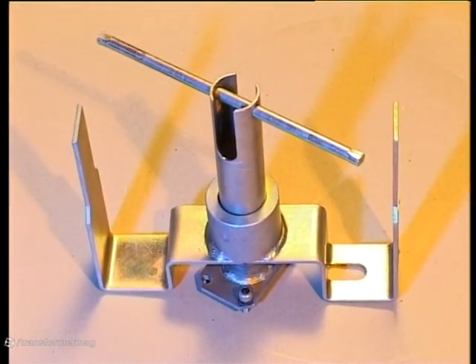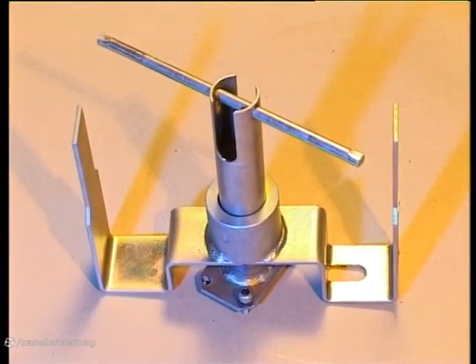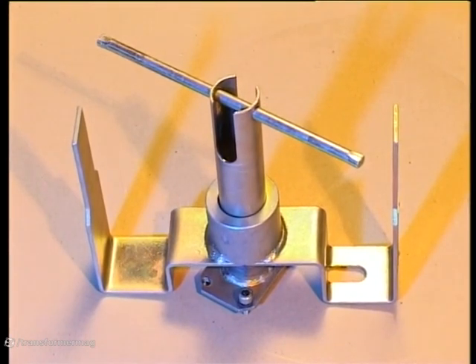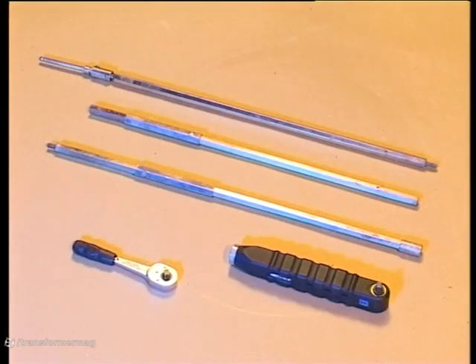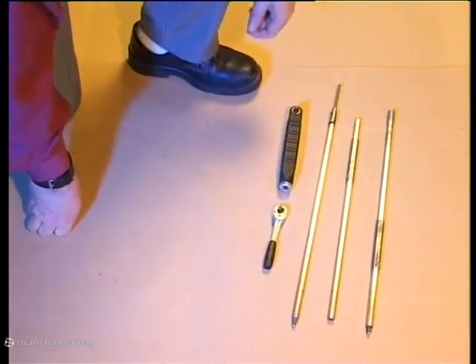The lifting and turning tool is used when lifting the tap changer insert and to rotate the insert to the correct position for removal. The screwing tool is used when installing and removing fixed contacts. A torque wrench capable of tightening to 12 Newton meters must be included. This is how to assemble the tool.